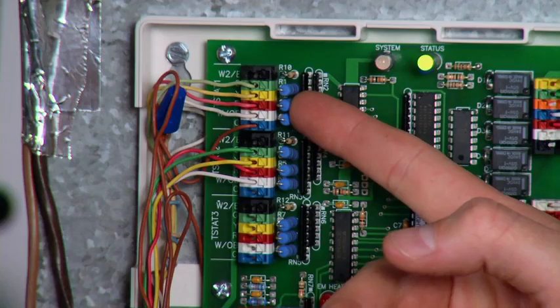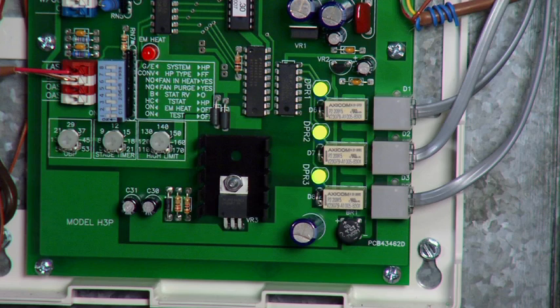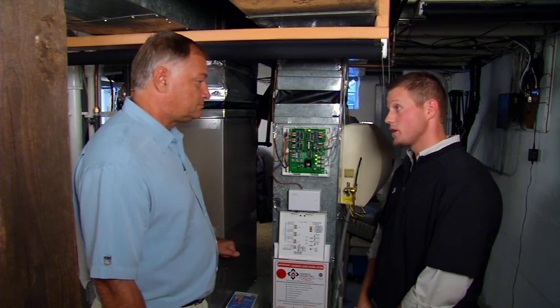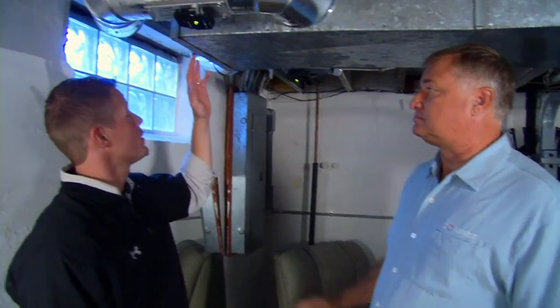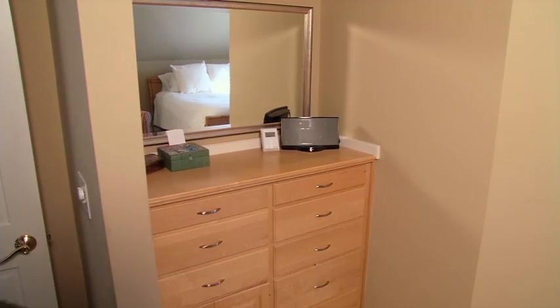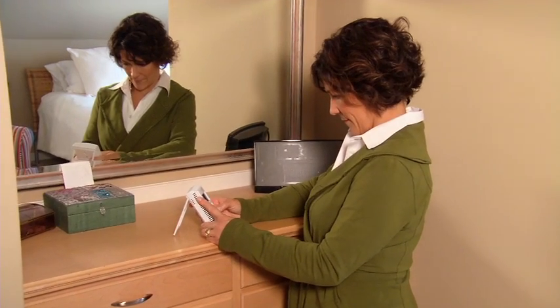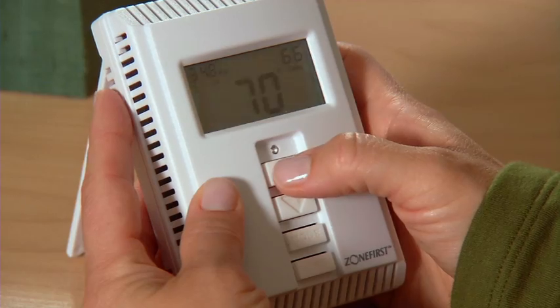The thermostats wire to color-coded push-in terminals. I see the LEDs will help you on system status when you go to check the system out. Yes. You also used a wireless receiver down here — yeah, it saved us a lot of time because we didn't have to fish wires to the second level. Bill, I see you've done some duct modifications here. Originally this trunk line was extended to here, so we had to shorten it up to accommodate a damper in this branch run. Sometimes minor duct modifications are needed. Here we decided to go with a wireless thermostat because we didn't have a common chase to run a wire to one of the upstairs bedrooms. The wireless stat saves us a ton of time not having to pull wires from upstairs.